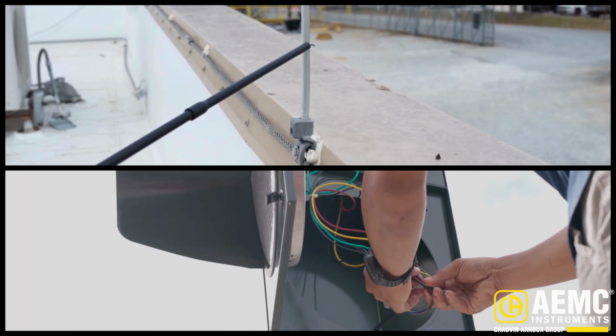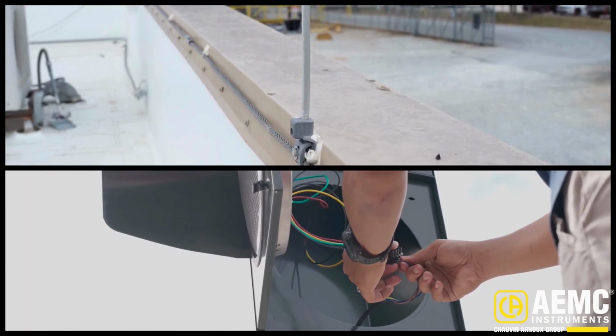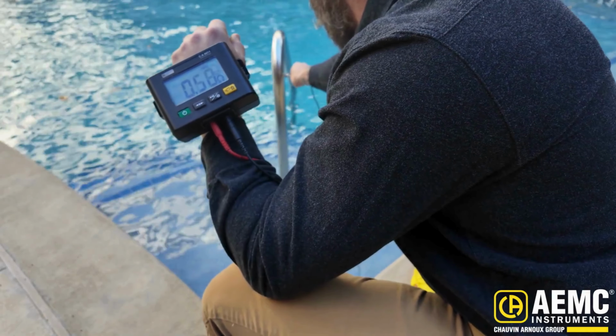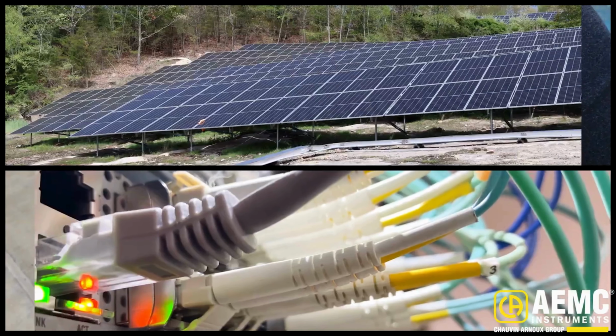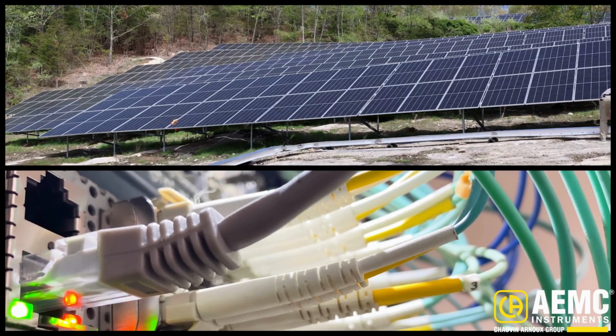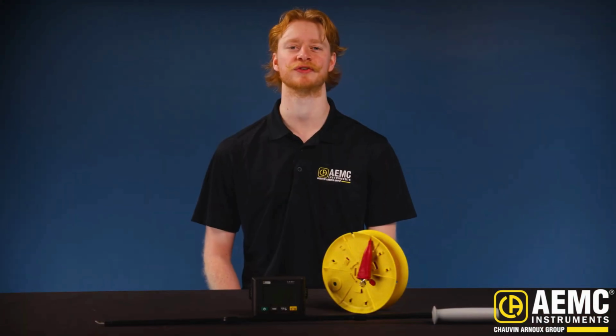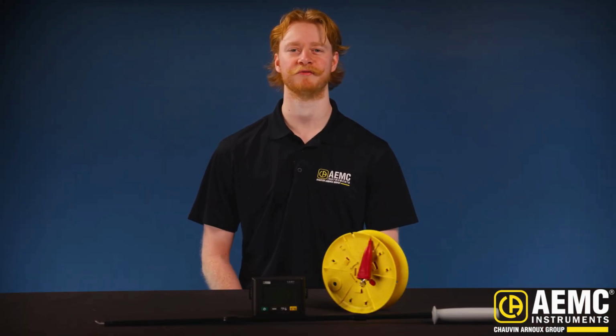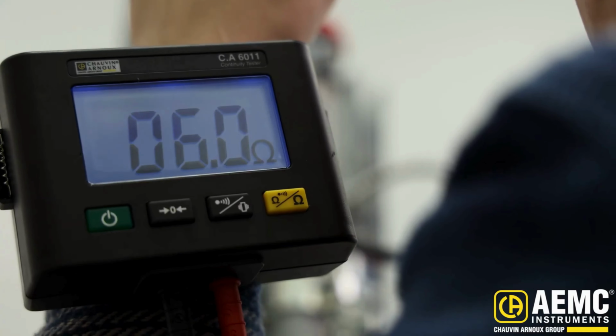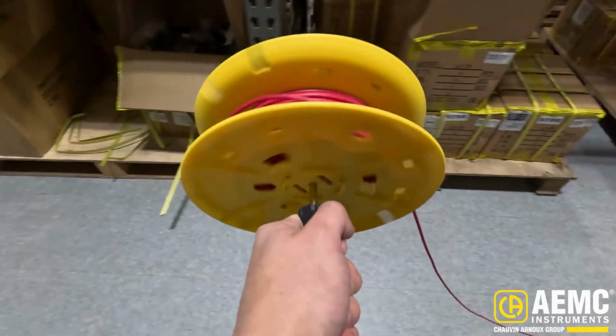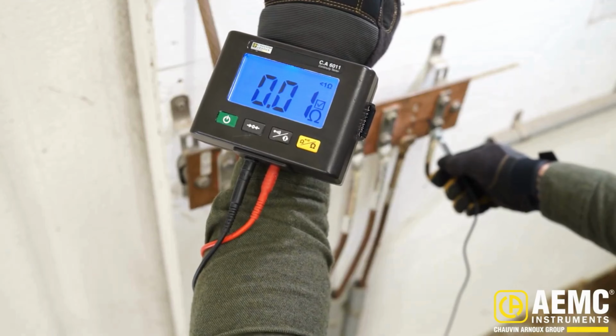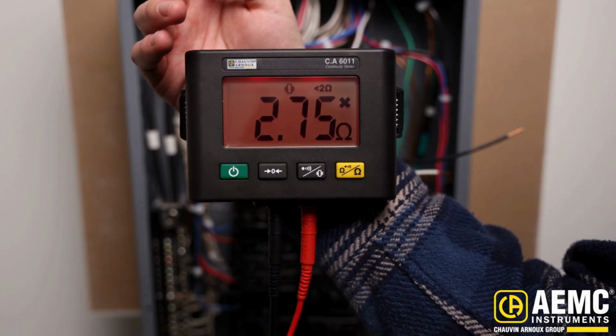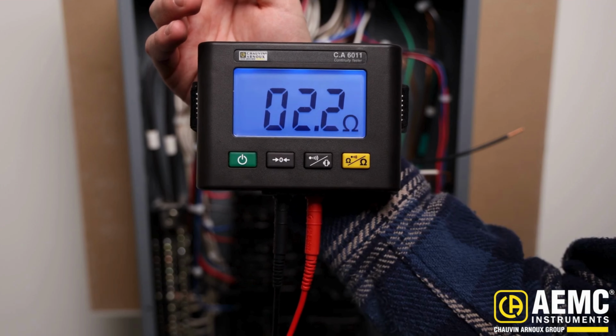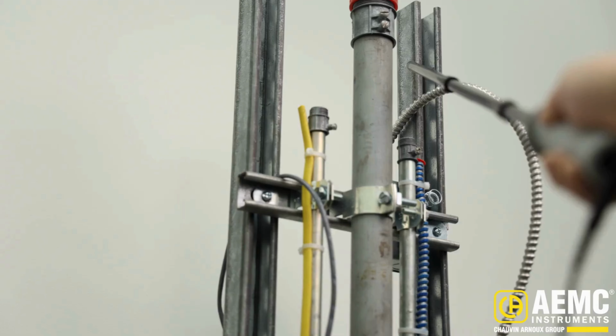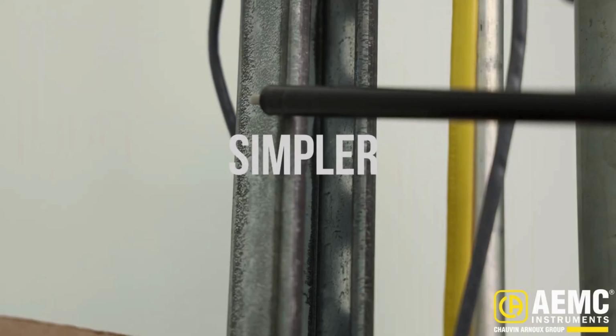Across applications ranging from lightning protection and traffic control, to bonding verification in swimming pools, solar farms, data centers, and utility installations, the model CA6011 offers a dependable, straightforward method for confirming low-resistance connections where safety is critical. With its wrist-mounted design, long-range reel, clear pass-fail feedback, and robust safety features, the model CA6011 continuity tester from AEMC Instruments makes long-distance continuity testing faster, simpler, and more efficient.